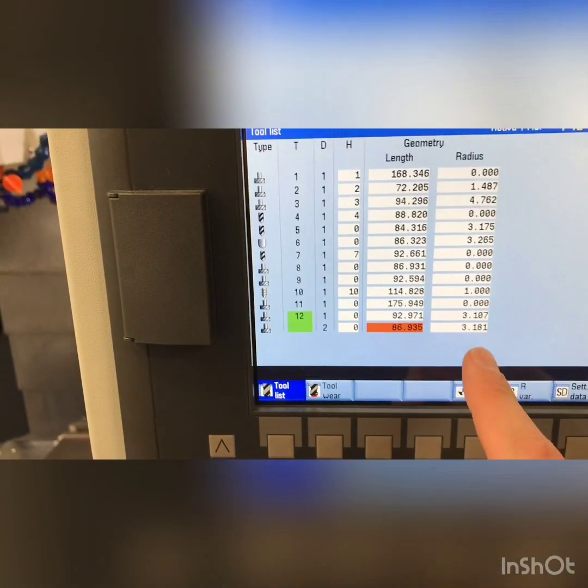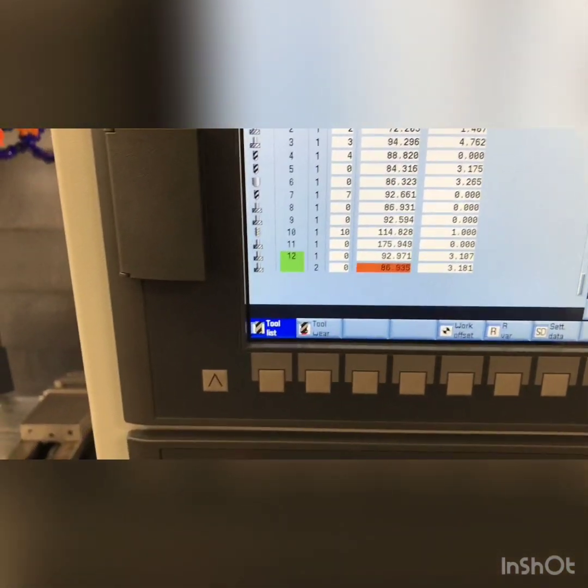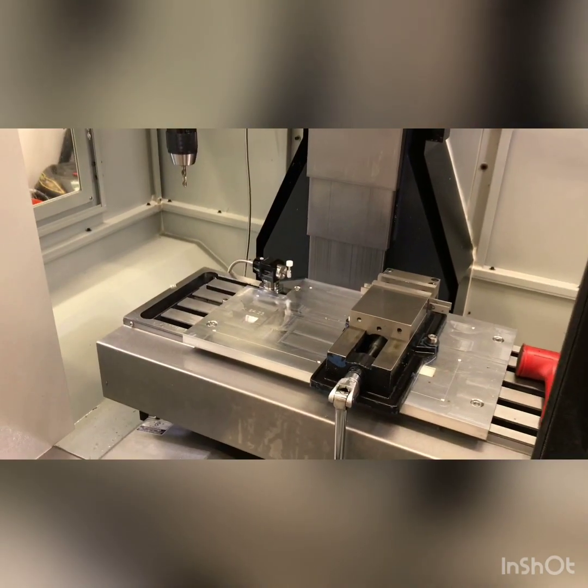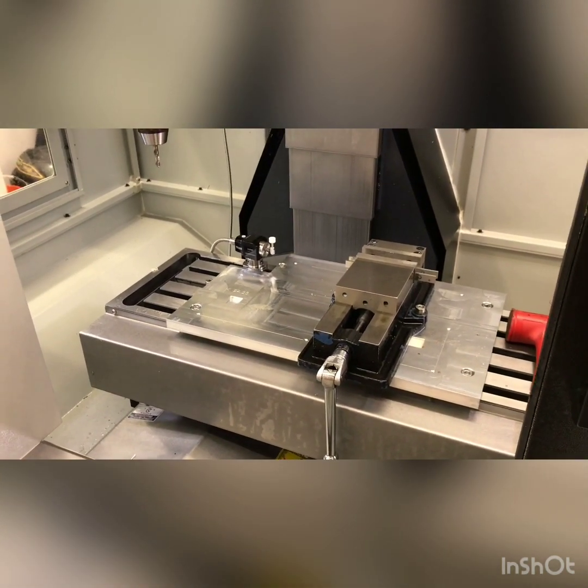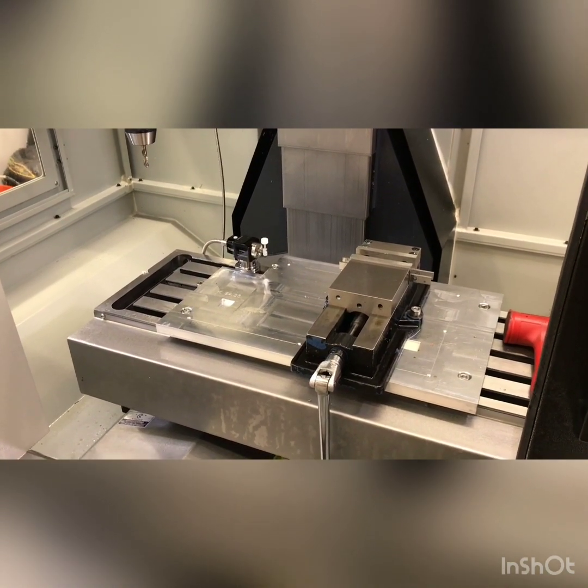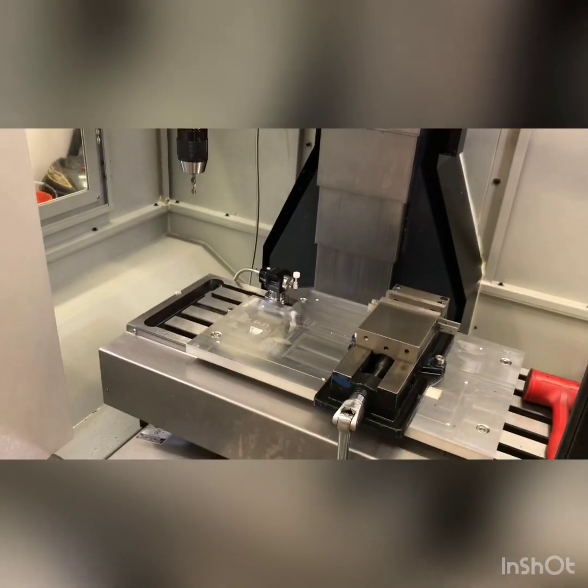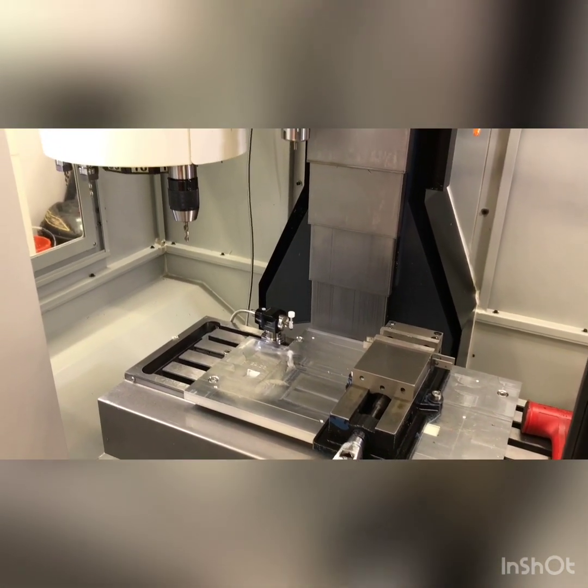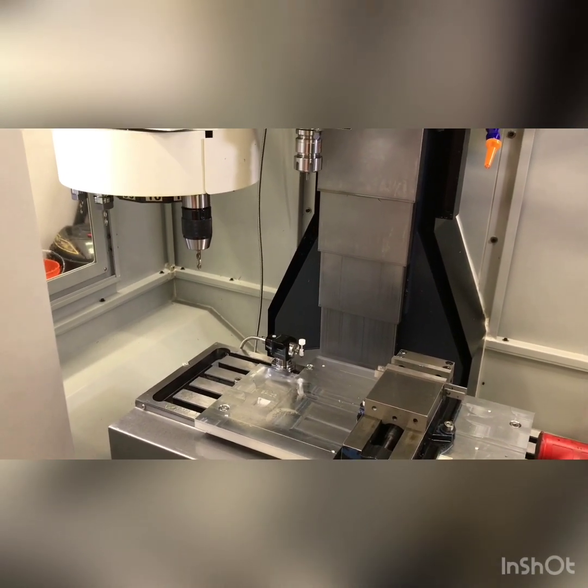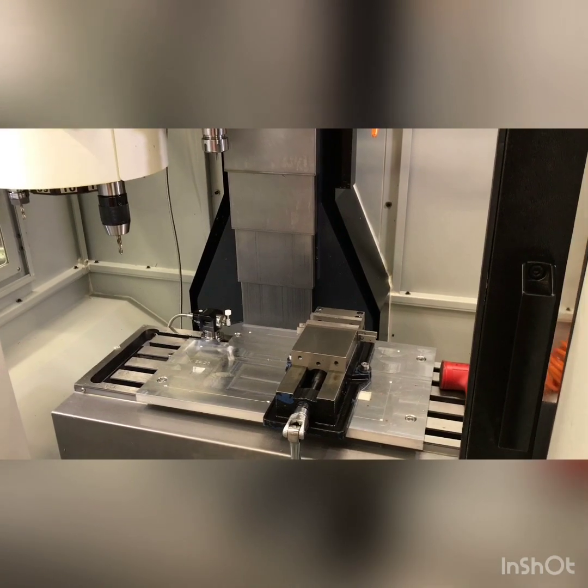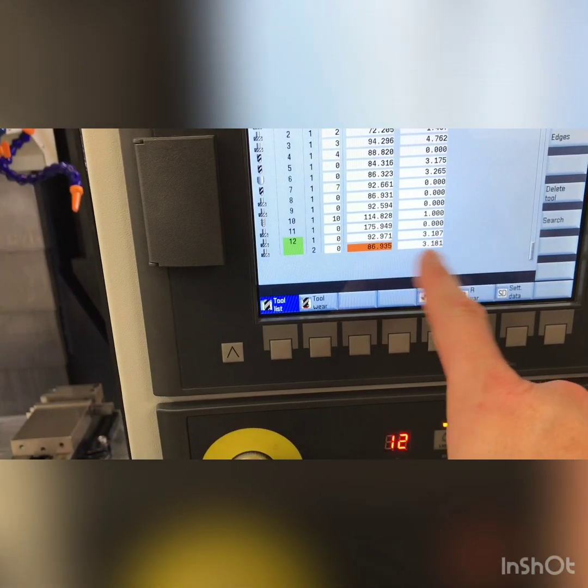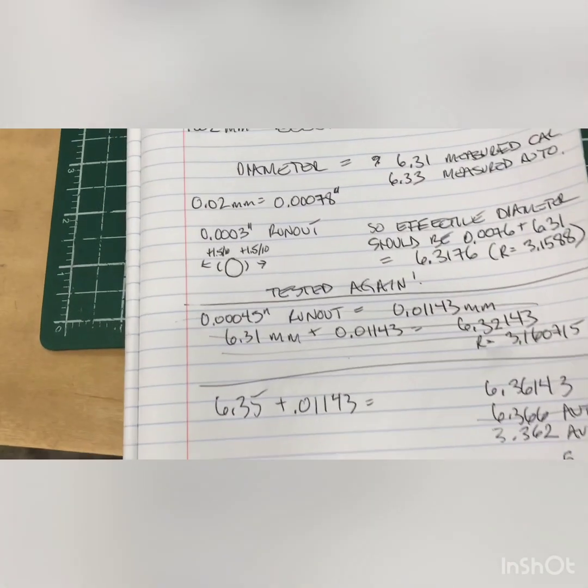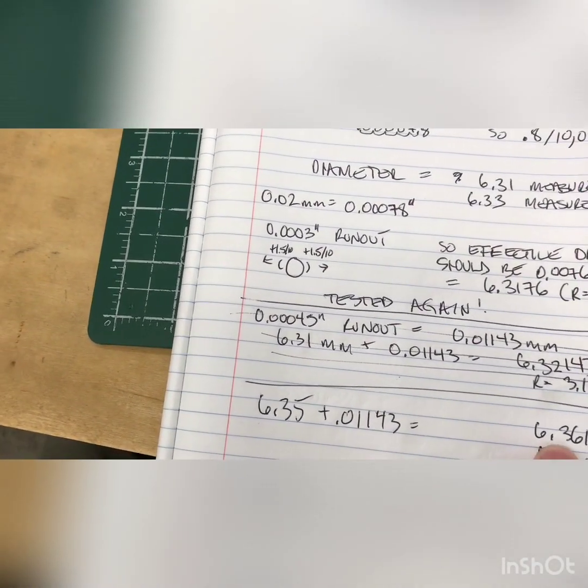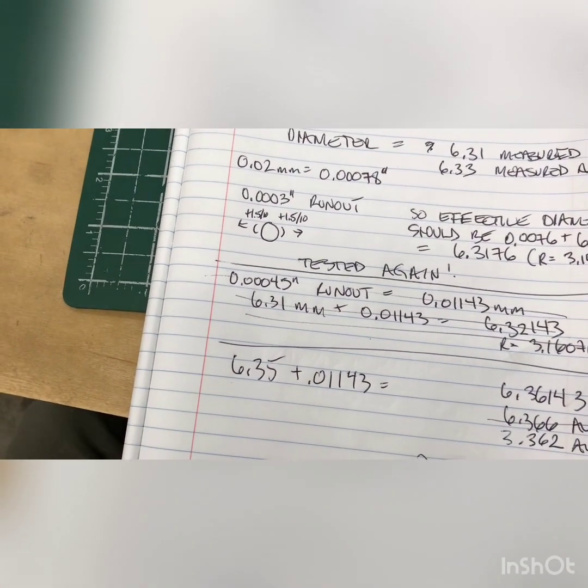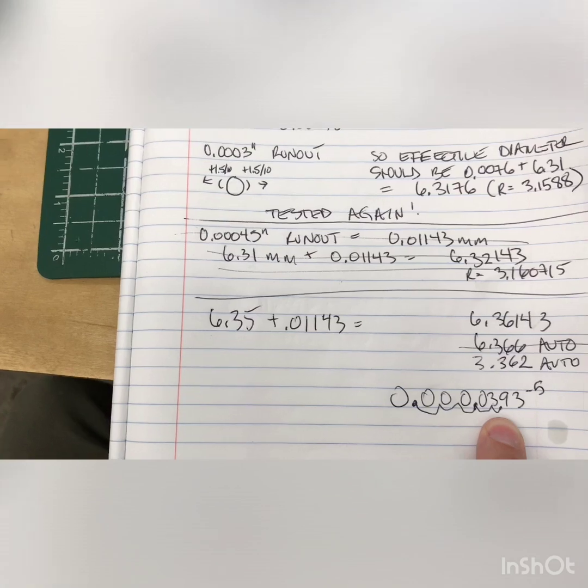And I ran the diameter again, so I'm not cheating on the actual calibration. I'm using 12.7, which is the calibrated diameter of the stylus, and I'm still using 6.35 because it's not rotating. So there's some fudge in there about where it's touching as opposed to where it's sitting in its elliptical path around the spindle. But the radius is 3.181, so when you multiply that by 2, you get 6.362, and I calculated when it's rotating the diameter should be 6.3614. So it's a difference of basically half a tenth.